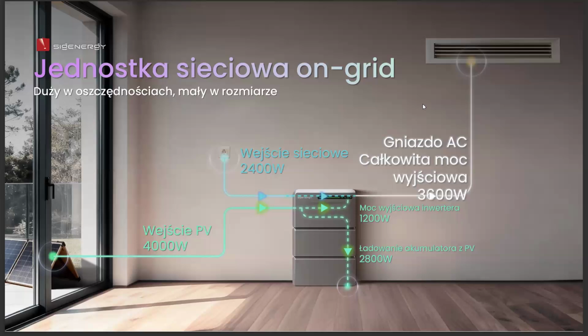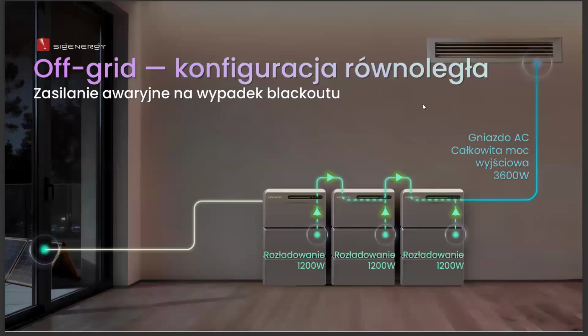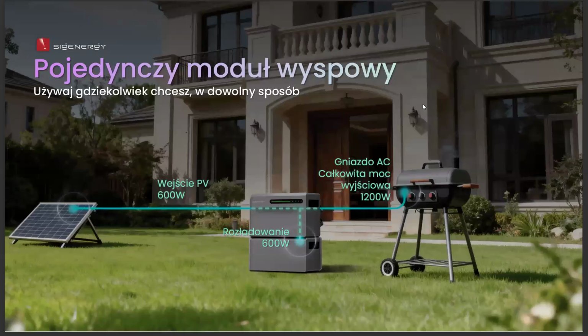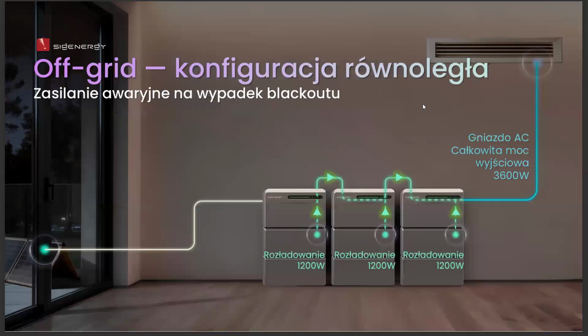3. AC output and mobility, camper and boat. The system is also highly flexible in terms of output power. Grid output, socket connection up to 800 W, to remain compliant with balcony micro-installation regulations and avoid unnecessary formalities. Dedicated output, a 3.6 kilowatt socket for higher power loads in island/off-grid mode.